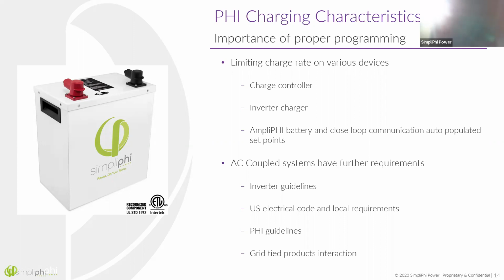If you've got an IQ8 on the roof, you're looking at 240 volts. That 240 volts is either on or off. And so when those AC coupled systems are used for charging, we don't have that same dial that we do with MPPTs. So we have to be even more careful with AC coupled systems to always make sure that the batteries are sized as twice the number of kilowatt hours as the number of kilowatts for an AC coupled system.